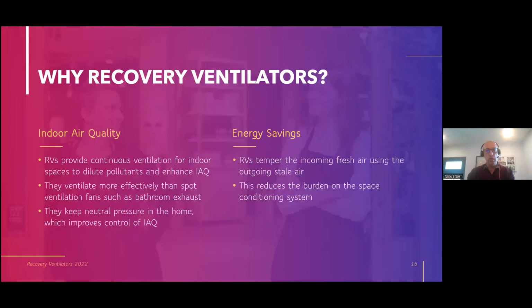So let's start with why we should be considering recovery ventilators. First and foremost, they're indoor air quality solutions. They provide continuous mechanical ventilation for our indoor spaces. And the reason mechanical ventilation is important is it dilutes pollutants and thus enhances indoor air quality. We'll talk more about that concept. They're much better at ventilating a house or a building than spot ventilation fans like bathroom exhaust fans. Yet bathroom exhaust fans are typically the solution that most projects use for indoor air quality. And I would argue that they're vastly insufficient to really ensure good IAQ throughout a building.